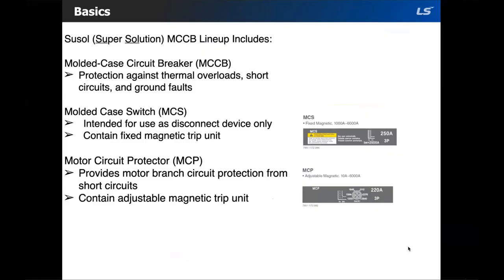They contain a fixed magnetic trip. Then there is the motor circuit protector, or MCP. As their name implies, they are intended to protect motors. MCPs are an instantaneous circuit breaker that contain only an adjustable magnetic trip unit.